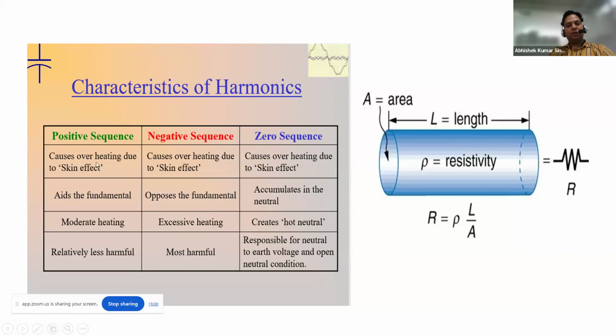Now, as we discussed above, skin effect. As you know, the harmonic current travels from the load to the source. If there is a load, such as a VFD, and harmonics are generated there, that harmonic will tend to travel up to the source. Why will it travel up to the source? Because the source has a low impedance. As you know, we have a transformer. If suppose there is a transformer of 2.5 MVA, then the impedance will be 6.25% only. So the impedance is very low, and that's why it will try to move up to the source.